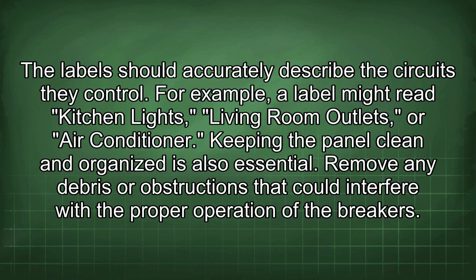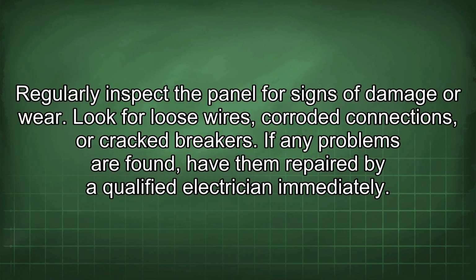The label should accurately describe the circuits they control. For example, a label might read kitchen lights, living room outlets, or air conditioner. Keeping the panel clean and organized is also essential. Remove any debris or obstructions that could interfere with the proper operation of the breakers. Regularly inspect the panel for signs of damage or wear. Look for loose wires, corroded connections, or cracked breakers. If any problems are found, have them repaired by a qualified electrician immediately.